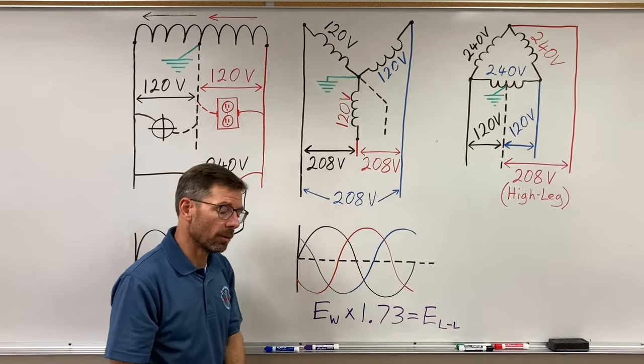How do I get that 208? I have a full winding and half a winding. If you draw 120 on one side of the triangle, 240 on the hypotenuse, drop it straight down for a right triangle, and use C² − A² = B², you get 208 volts. There are code requirements: the high leg must be colored orange or identified by some other means, it should be on B phase in panels, and there must be a sign stating that B phase to neutral is 208 volts — so we don't accidentally connect 120-volt loads to 208 volts and blow things up.